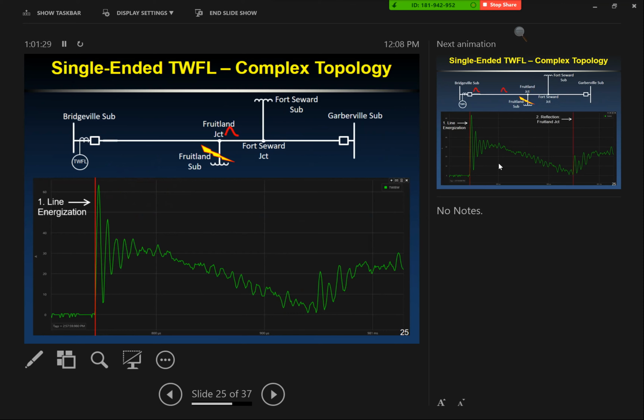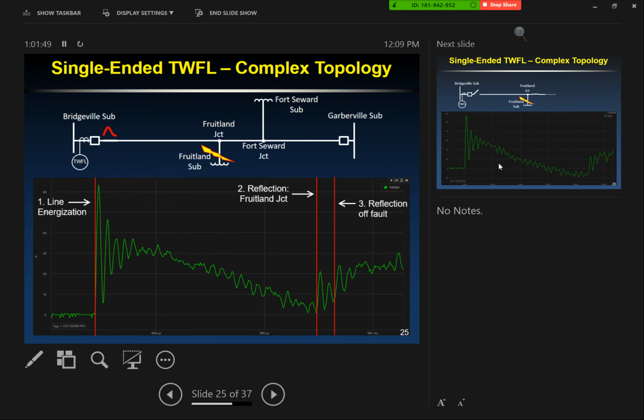So the traveling wave goes down to Fruitland Junction. What we expect at Fruitland Junction is we'll see a reflection back off the junction, and we'll see part of it continuing on down to the faults. So you get that. That point arrives, that's your reflection off of Fruitland Junction, positive polarity. And then finally your reflection off the fault arrives. So this you might have a chance actually doing a fault location off of. I think you kind of got lucky with the relative position of where this is. If it were closer to Fruitland Junction, it'd be buried in this noise. Or if it were closer to the bank, you might get more noise on that side. So it's not a perfect picture, but in hindsight, we could say, yeah, that's where the fault is.